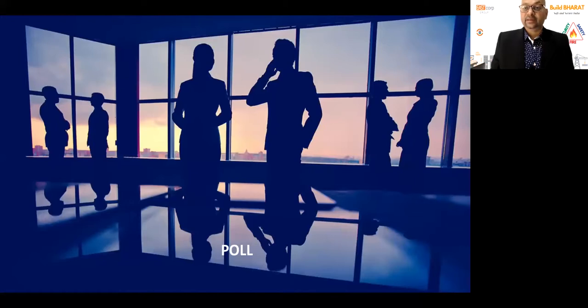This is not me saying it, it's NFPA 25 saying it's absolutely okay if you don't inspect areas which are inaccessible, difficult to access, or specifically concealed spaces - meaning above false ceiling areas or areas you cannot see. It's absolutely fine because it's assumed the system performance is checked. As long as you're monitoring it at the ground level, at the performance level, it's absolutely fine, you don't need to access it. Very simple thing, but I think it gives a lot of clarity on how these courses will help clarify your doubts and gain clarity in maintaining the system.